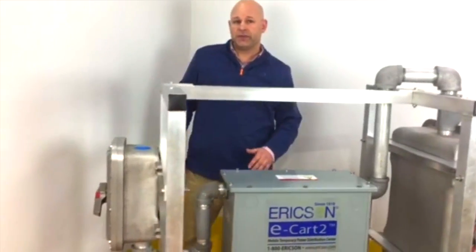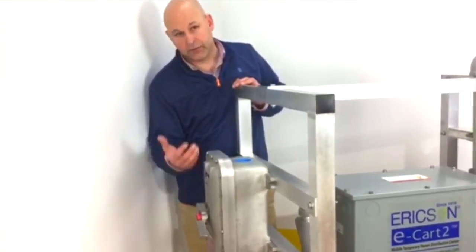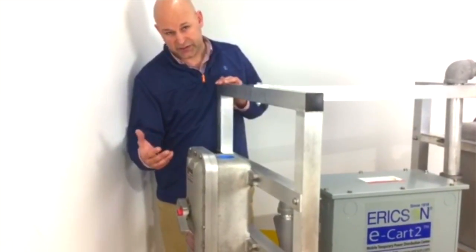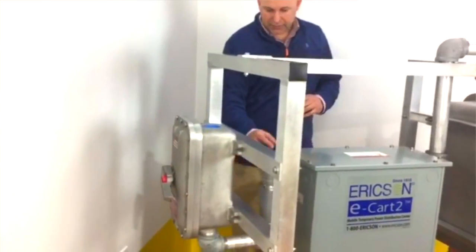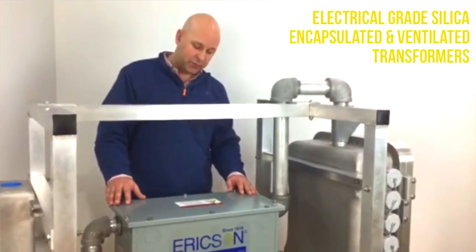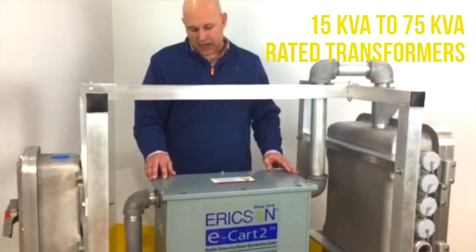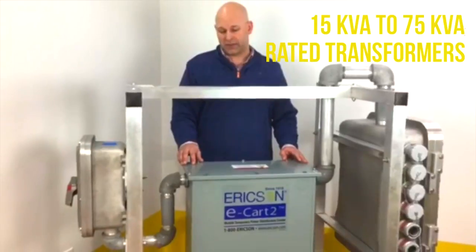Some features and benefits on the E-Cart II platform: we have a primary disconnect. This comes in a variety of sizes, and it's fully sealed Class 1-2 equipment as mentioned — fully enclosed, sealed piping from primary to our transformer. This transformer is 45 kVA, and our standard units come in 15 kVA to 75 kVA.